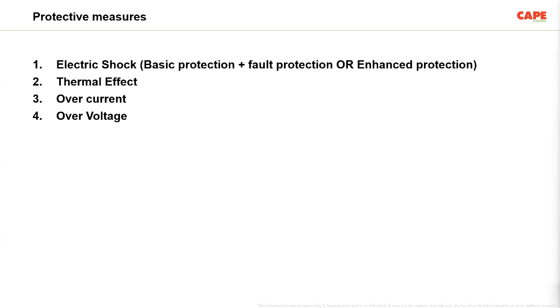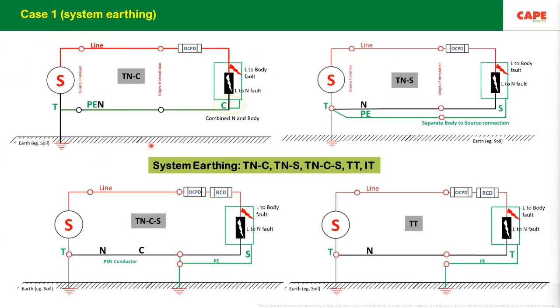And then the final one is over voltage protection: protective measures against temporary over voltage, sustained over voltage, transient over voltage, harmonics, and so on. All these 4 safety measures are mandatory in an electrical installation. And now these 10 points, which I am going to explain, are basically required to achieve these safety measures. The first one, the fundamental one, is called system earthing.